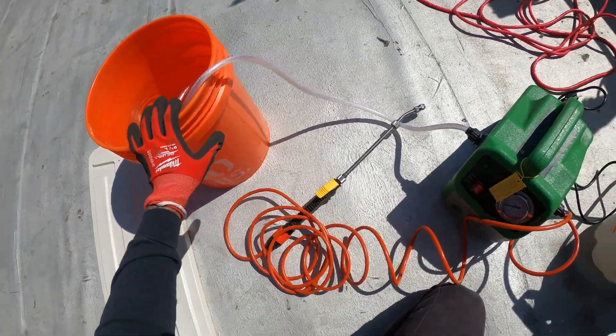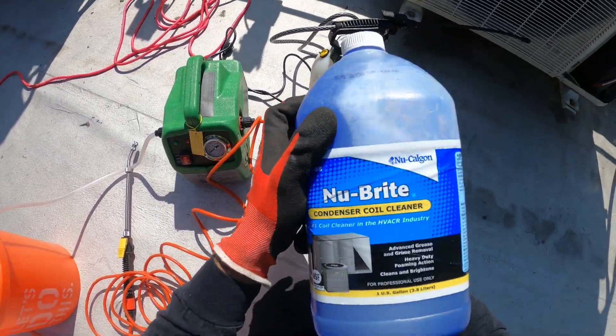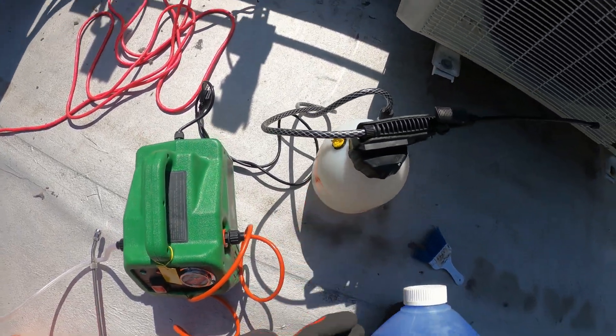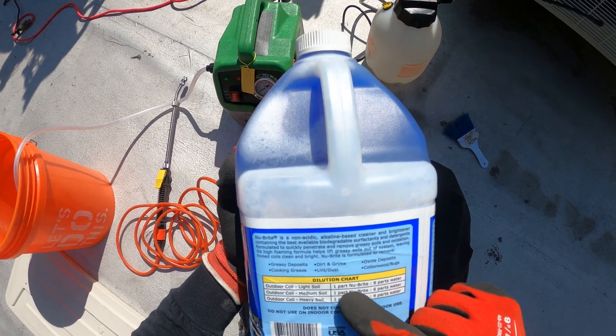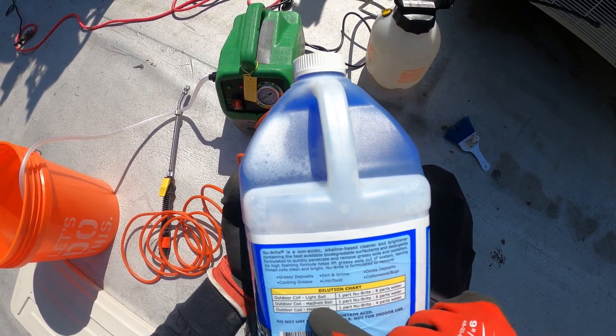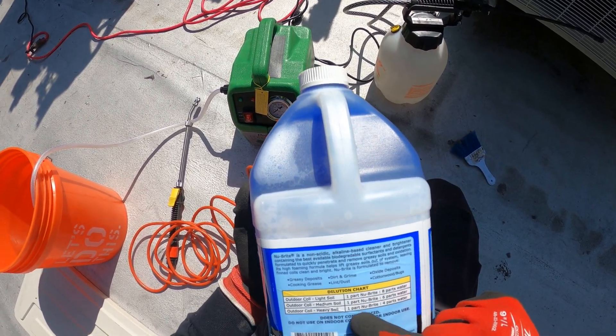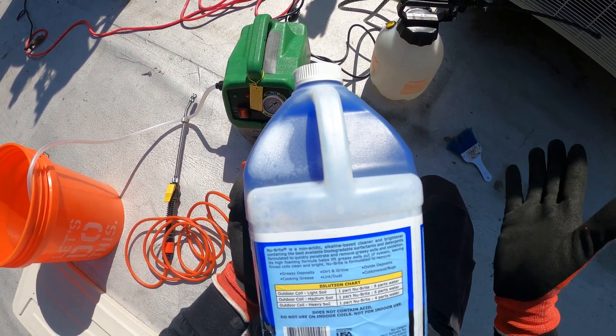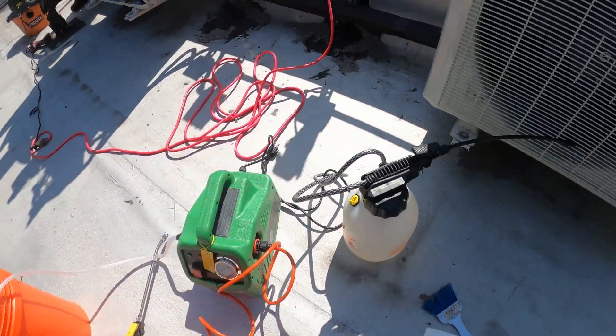I've got the pressure washer set up and a bucket, and now we're going to mix the Nu-Brite condenser coil cleaner with water. For light soil: one part Nu-Brite, eight parts water. Medium soil: one part Nu-Brite, six parts water. Heavy soil: one part Nu-Brite, four parts water. So let's go ahead and mix this up and apply it on our coil.